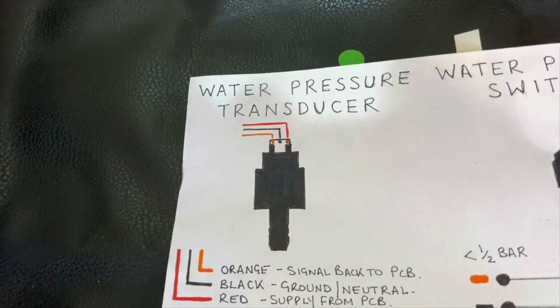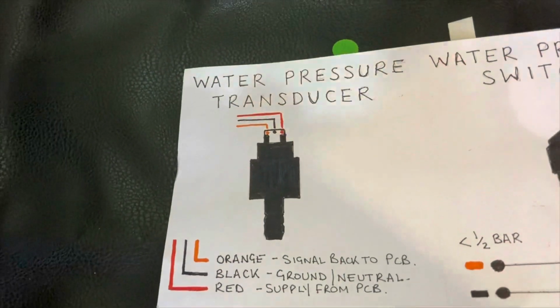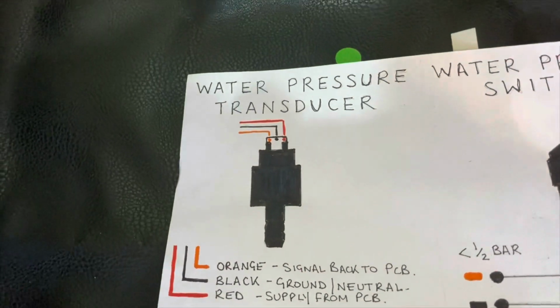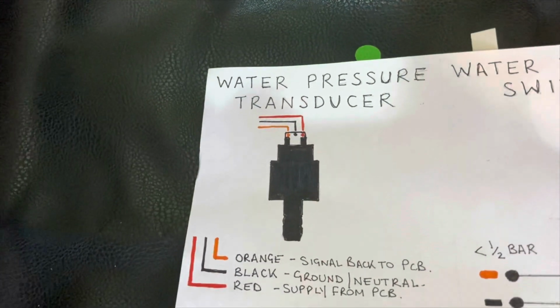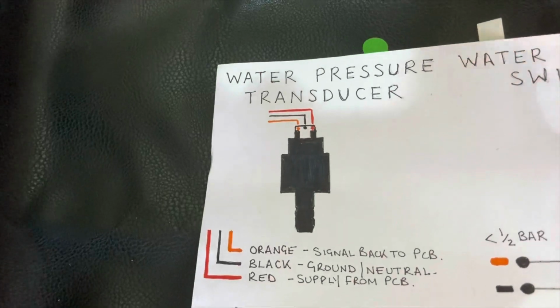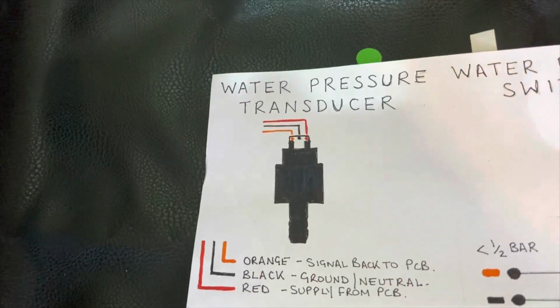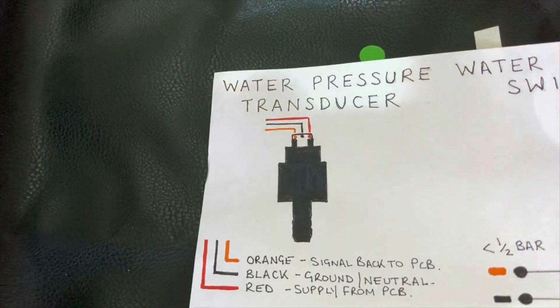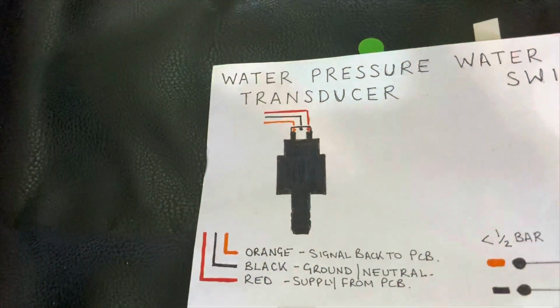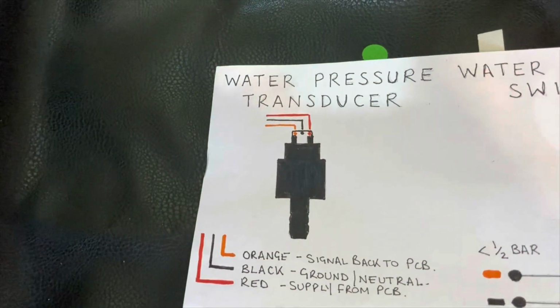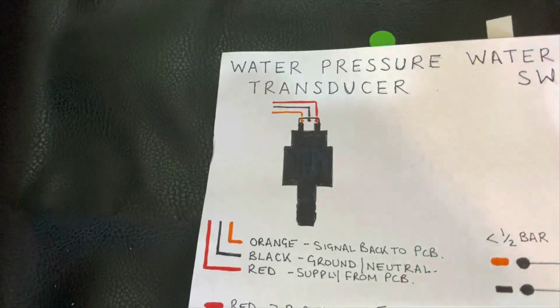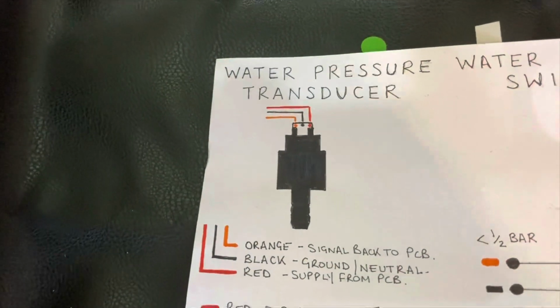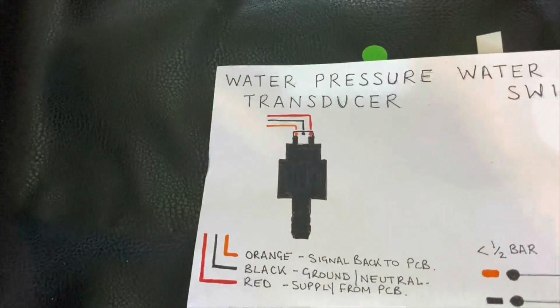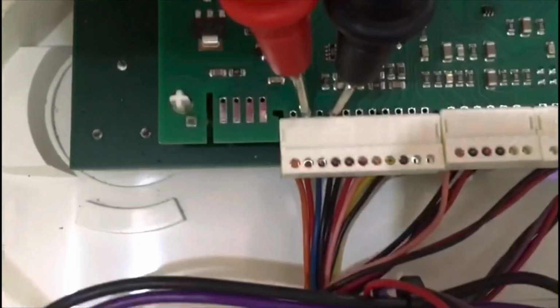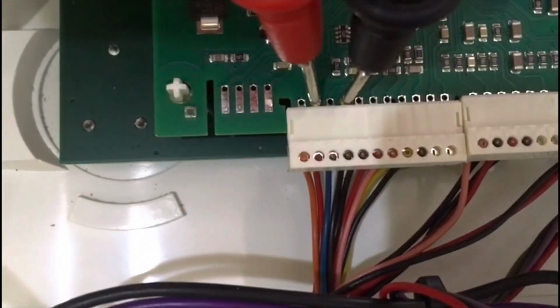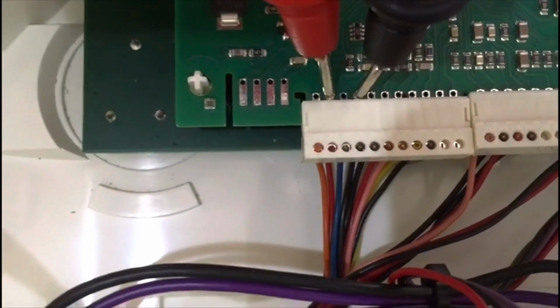When you're testing a transducer, you can't really do a dead test, if you will. I've seen somebody do that before on YouTube, and it really doesn't make any sense. You tested the resistance for it, and it really doesn't tell you anything, to be fair. You've got to do it live, so make sure you've done all your electrical checks, you're working safely, you know what you're doing. Make sure you're working safe at all times.